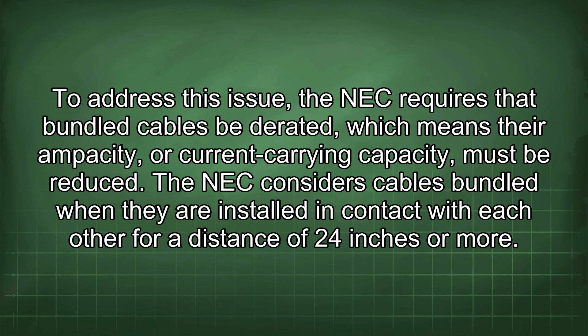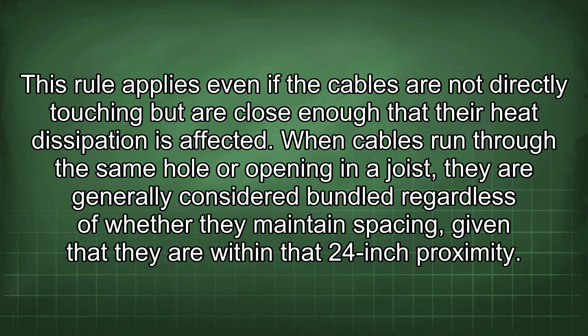This rule applies even if the cables are not directly touching but are close enough that their heat dissipation is affected. When cables run through the same hole or opening in a joist, they are generally considered bundled regardless of whether they maintain spacing, given that they are within that 24-inch proximity. The derating factor is applied to compensate for the reduced ability of the cables to dissipate heat.